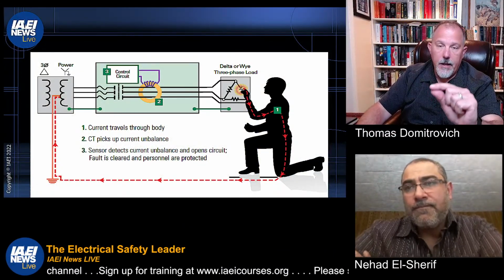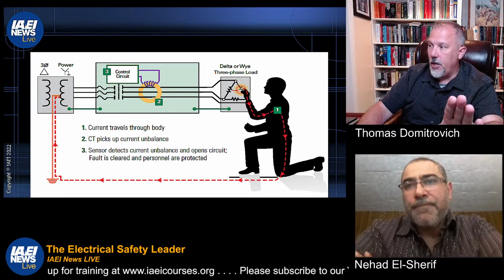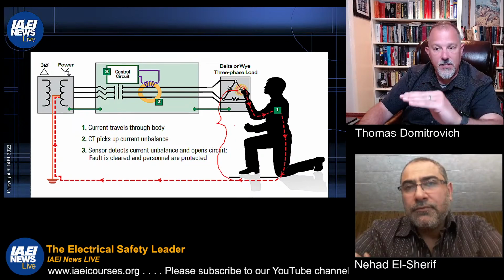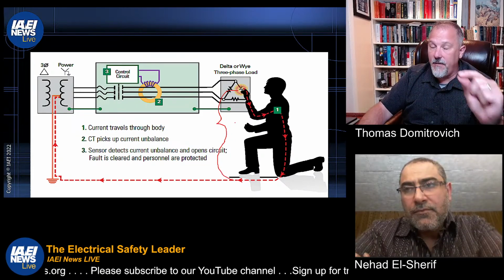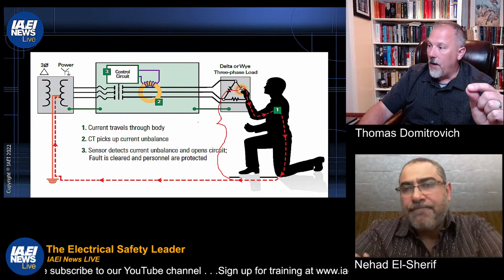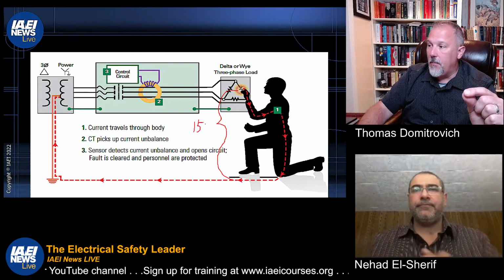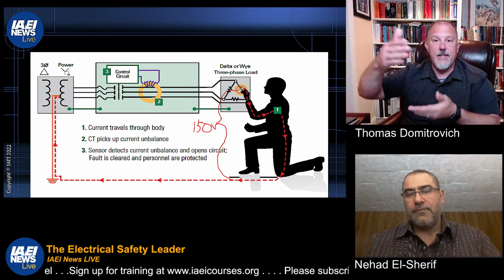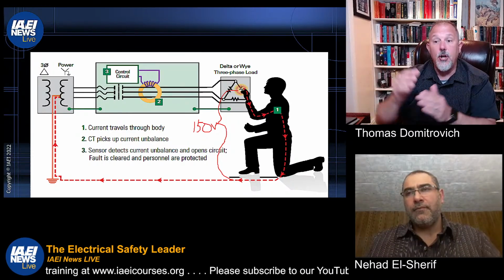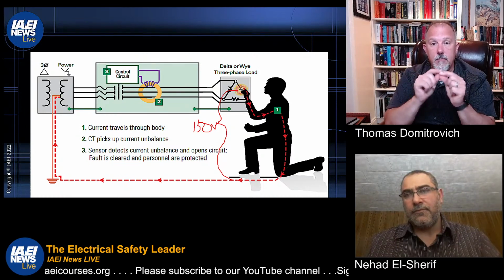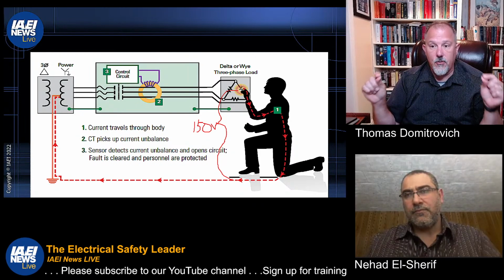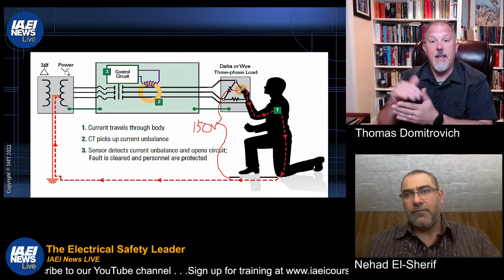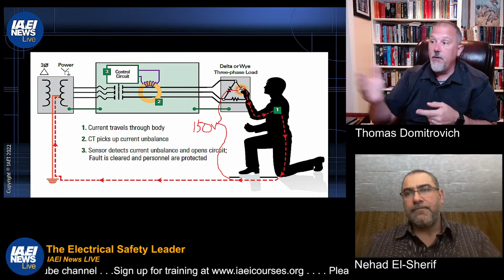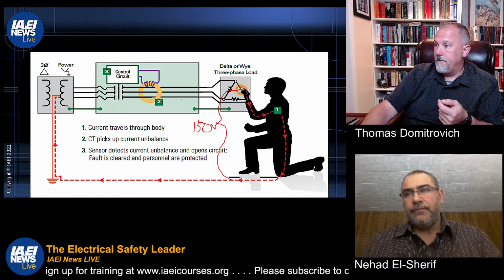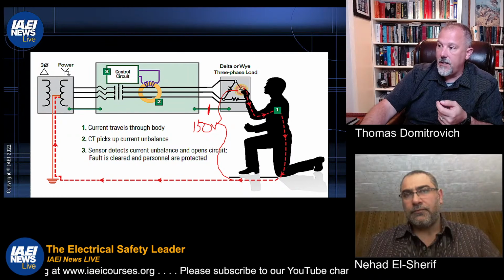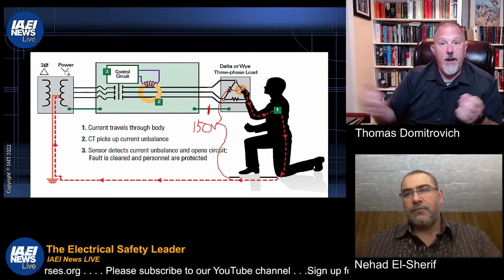And what you're doing, and help me describe this, is you want to make sure that the voltage across the body doesn't exceed a certain value, right? Right. What's that? 150 volts. 150 volts. So we don't want the human body, whoever's connected from line to ground, to have a voltage greater than 150 volts. So what you're doing in this special purpose GFCI is monitoring that equipment ground, that ground connection, so that you limit that voltage. And if it's not there, then you can trip. So if for example you break this connection, it could trip just because you no longer have that equipment ground.